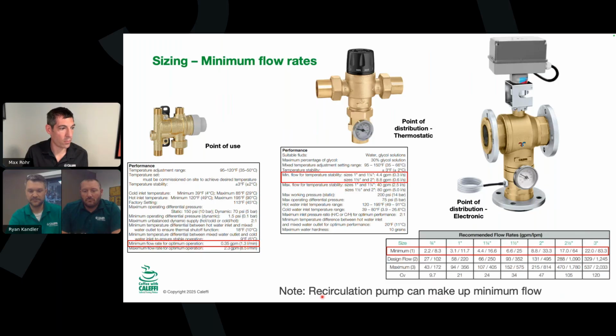Yeah, and that's important to note because you will see that temperature. We've got the outlet gauges for these different mixing valves, and you will see that hunt a little bit if you're below, in this example, the 2.2 GPM. If you did not have a recirc pump or the recirc pump was turned off, and you have like 1 GPM of flow in that building, you would see that hunting to try and find the right temperature.